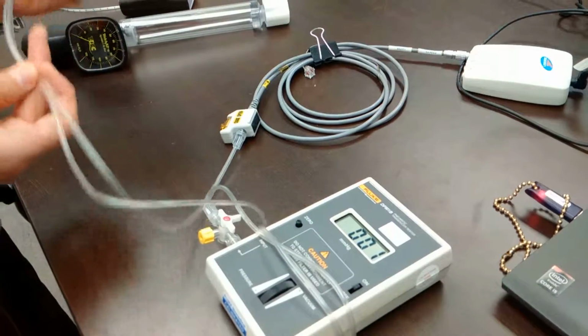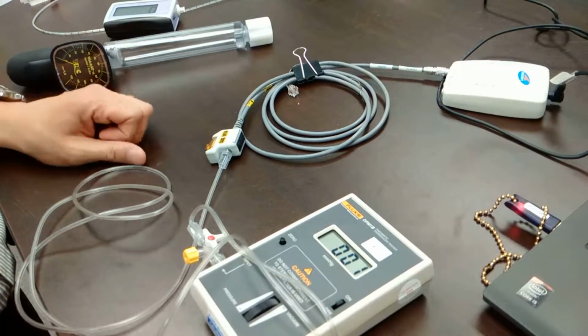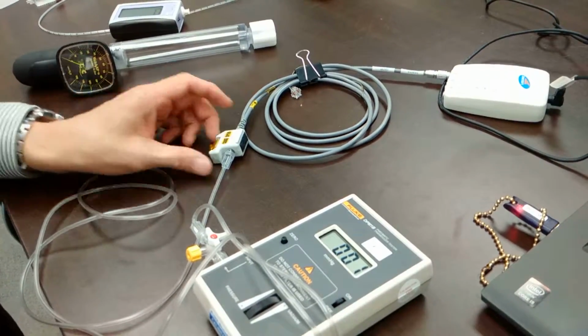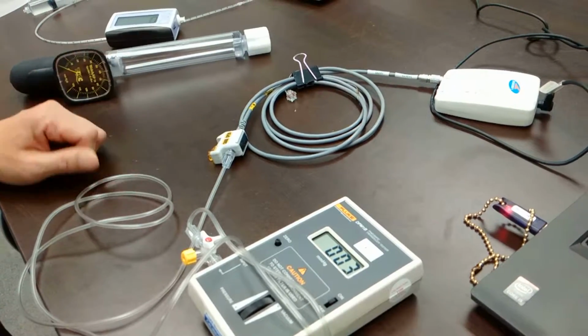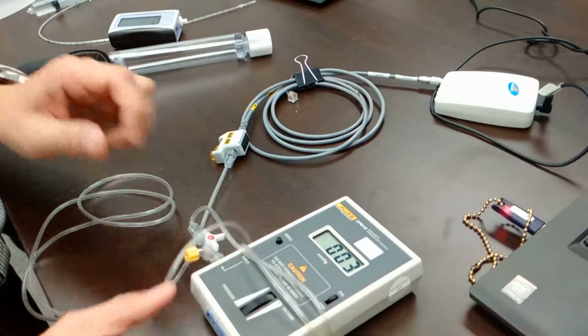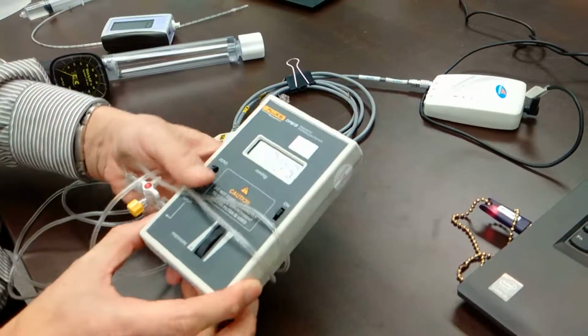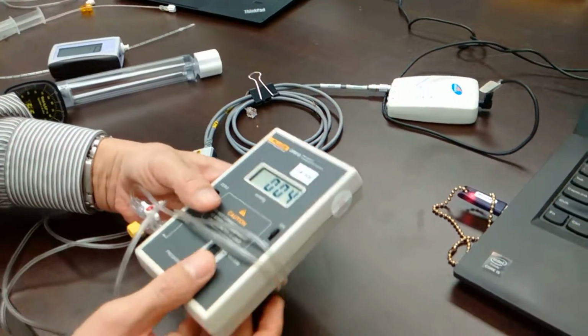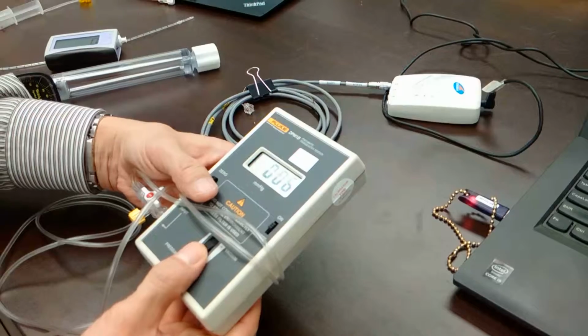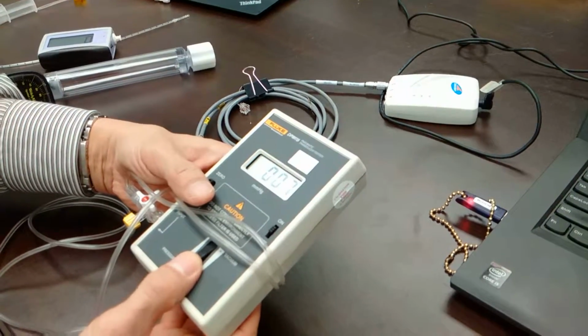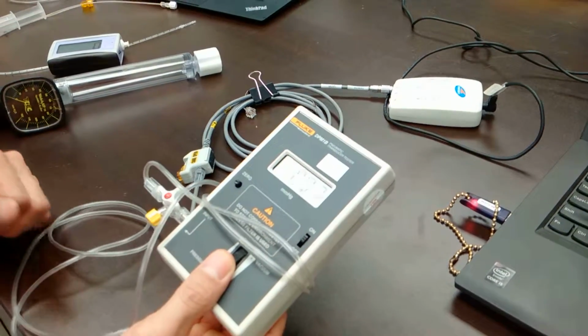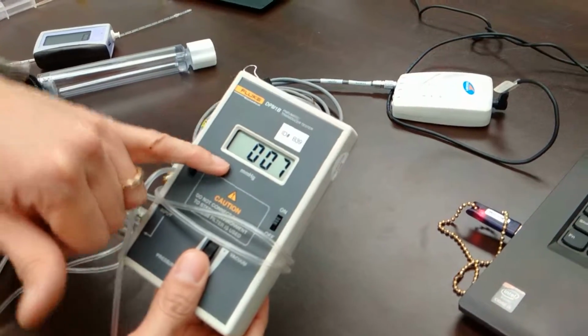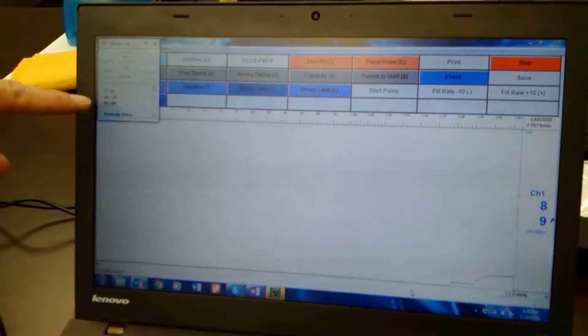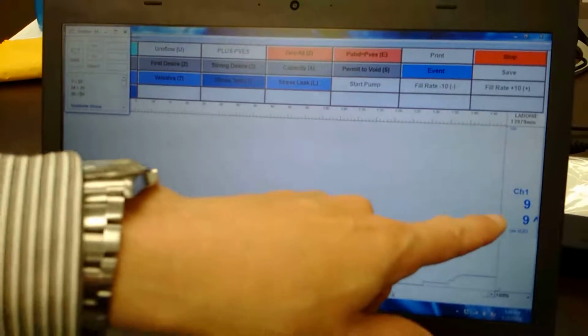So the way the calibration works is we make the connection so that we have this air tubing that goes directly from the calibrator to the charger. We put it in the charge position. That closes everything off. Okay, and then we can spin the dial to look at pressure values that we need to generate for the charger. So you see at 7, now this is in millimeters of mercury, we have a conversion table. 7 actually represents 10 centimeters of water, and you can see it's about 9, 10.